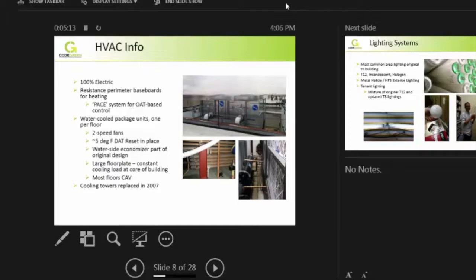In terms of cooling systems, you have one package AC unit on each floor, which I'll show you in a diagram I put together that shows how it is laid out in general. They do have 2-speed fans. At a minimum, they have a discharge air temperature reset, which is better than nothing, I guess, when it comes to a reset. Also, free cooling coils within the system, which was something the building itself had a lot of issues with over its entire operation.